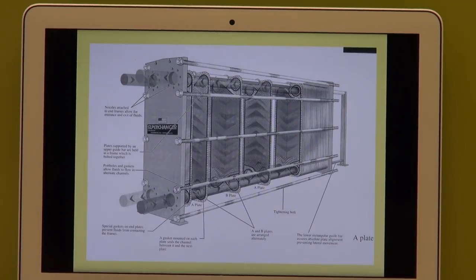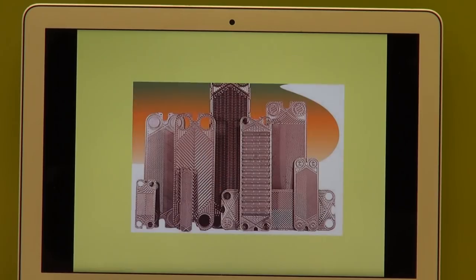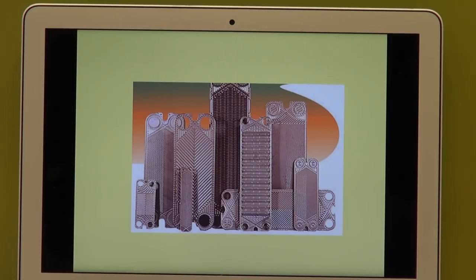Plate heat exchangers have different patterns on the plates and flow directions in opposite directions from each other. The plates can be framed or brazed to make them leak-proof. The patterns are designed to make the flow very turbulent, which enhances heat transfer. However, nature always gives you a curve ball: if heat transfer increases, your pressure drop increases — you cannot disconnect the two.